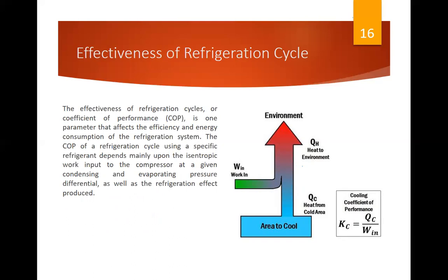Next is the effectiveness of the refrigeration cycle. The effectiveness of refrigeration cycles, or coefficient of performance, COP, is one parameter that affects the efficiency and energy consumption of the refrigeration system. The COP of a refrigeration cycle using a specific refrigerant depends mainly upon the isentropic work input to the compressor at a given condensing and evaporating pressure differential, as well as the refrigeration effect produced. This is also COP.